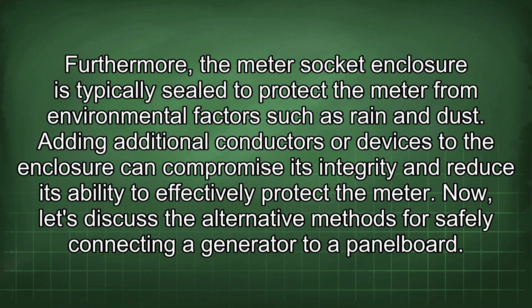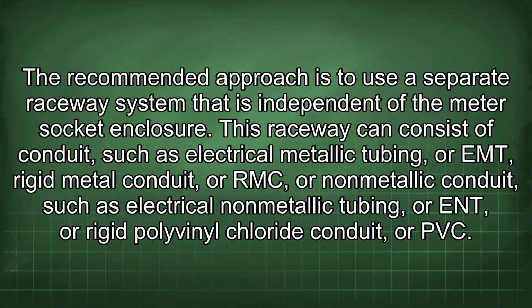Furthermore, the meter socket enclosure is typically sealed to protect the meter from environmental factors such as rain and dust. Adding additional conductors or devices to the enclosure can compromise its integrity and reduce its ability to effectively protect the meter. Now let's discuss the alternative methods for safely connecting a generator to a panel board. The recommended approach is to use a separate raceway system that is independent of the meter socket enclosure.